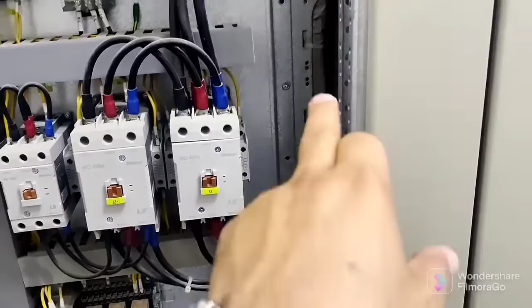3 wires will come here. From this main contactor it will go directly to the back side to the connector. This we will take from here for the delta purpose, and this also 3 cables, 1 pair, 3 pairs, will go to the connector at the back side, and these 3 will come here for the star purpose. You need to short these 3 contactors. And this is the control wires, going to the back side to the PLC, relays, timer switch.